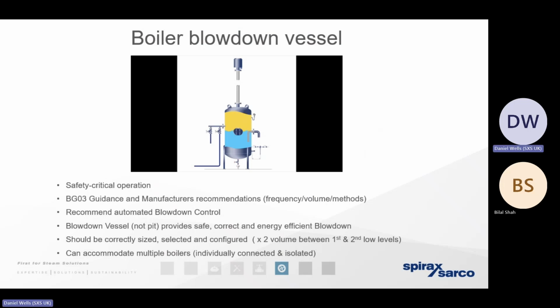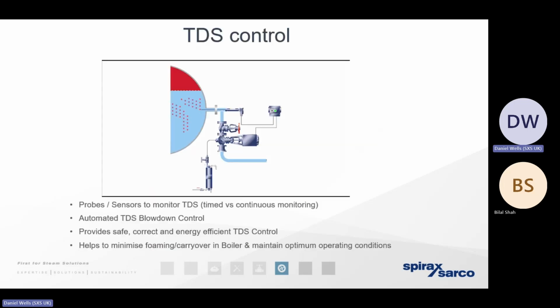But using my analogy, the bottom blowdown, that takes care of the sand in my cup of tea, the heavier particulate. We need to address the high water chemistry with the solids that are going to be held in suspension. That's what we call the TDS. We could perform the TDS manually. Better for us to do it automatically. If we do it automatically by means of having a conductivity probe, sending a signal to a modulating valve, it means we can ensure that that valve opens at the determined set point in terms of parts per million.